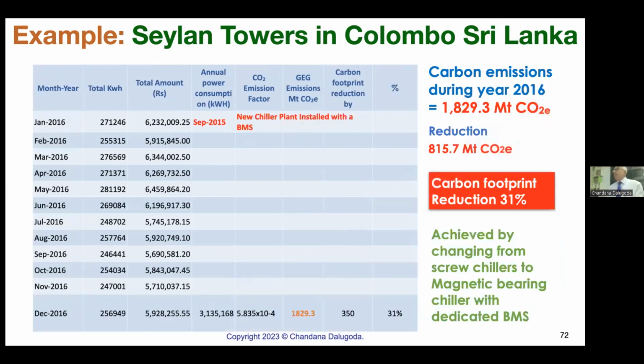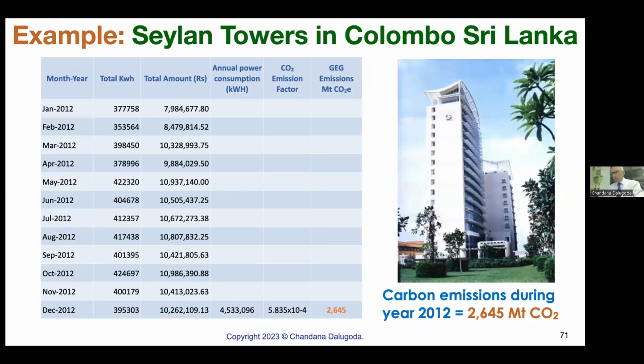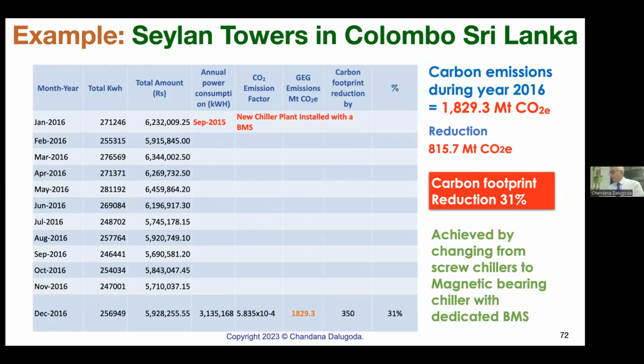But in 2015, we installed a very, very energy efficient magnetic bearing centrifugal chiller with an innovative building management system with energy saving strategies. The outcome in 2016 was that 4.5 million became 3.1 million kilowatt hours. Earlier, it was 2,645; the carbon dioxide became 1,829.3. That is a 31% reduction in carbon emission. This is green buildings. This is how we try to achieve carbon neutral also.